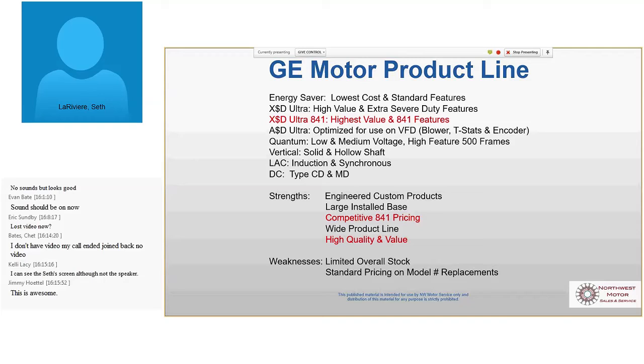They also make a couple other featured motors. This is ASD, which stands for Adjustable Speed Drive, and that one's optimized for VFDs. Now, this 841 motor works on a VFD. When I say optimized, on the back of that brochure, there's a picture of that type of motor. I lied, I'm sorry, there isn't.